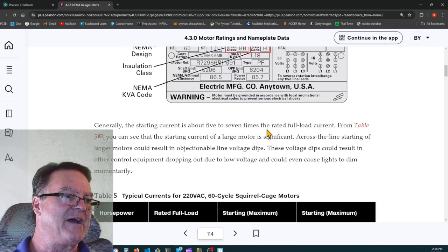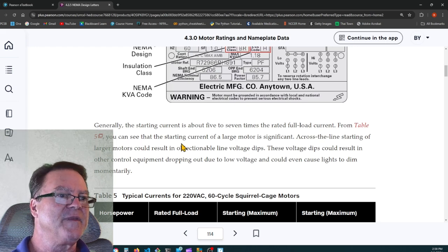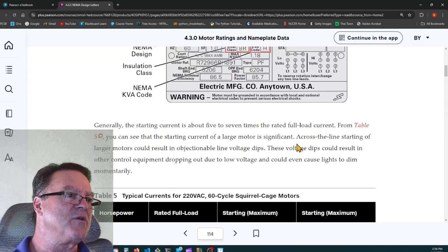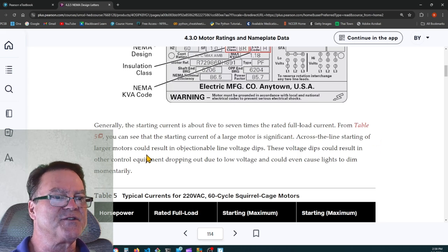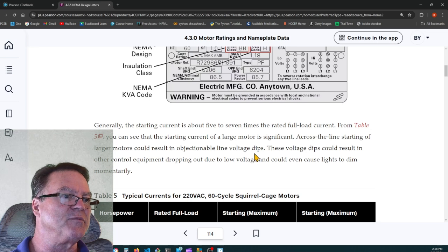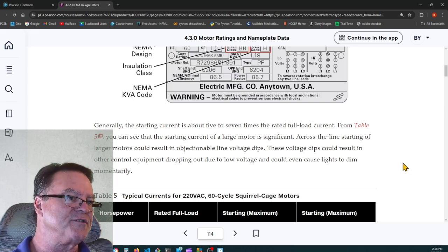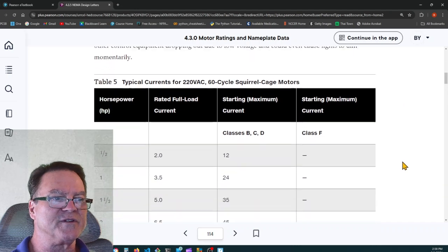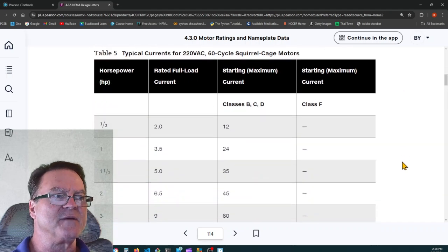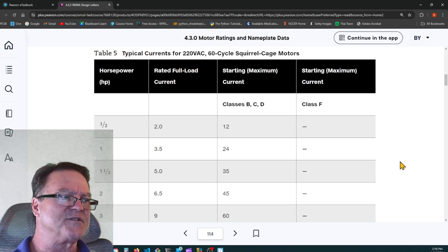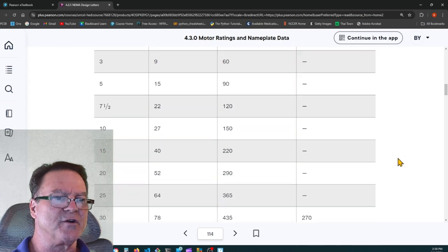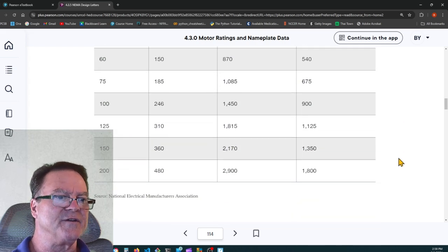Generally, the starting current is about 5 to 7 times the rated full load current. From table 5, you can see that the starting current of a large motor is significant. Across-the-line starting of large motors could result in objectionable line voltage dips. These voltage dips could result in other control equipment dropping out because of low voltage and could even cause lights to dim momentarily. So sometimes it's advisable to use a soft start or a variable speed starter so that you're not trying to start it at full load voltage. There are different types of soft starts.